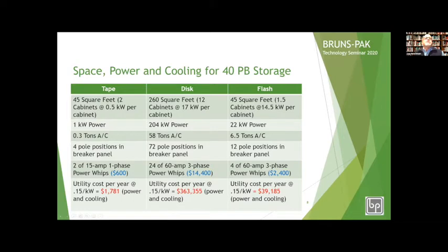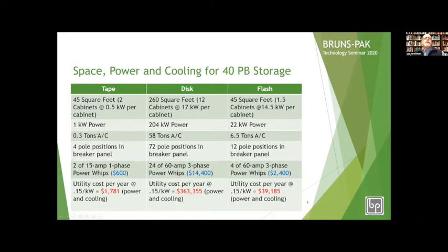Here's where it gets interesting. The tape is 45 square feet at 0.5 kW per cabinet. The disk — 12 cabinets, 260 square feet — is 17 kW per cabinet. The flash storage, back to 45 square feet in one and a half cabinets, is 14.5 kW per cabinet. The overall 40 petabyte solution is 1 kW of power for tape, 204 kW for disk, and 22 kW for flash storage.